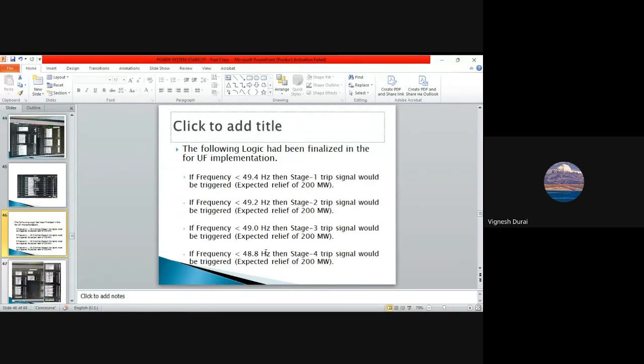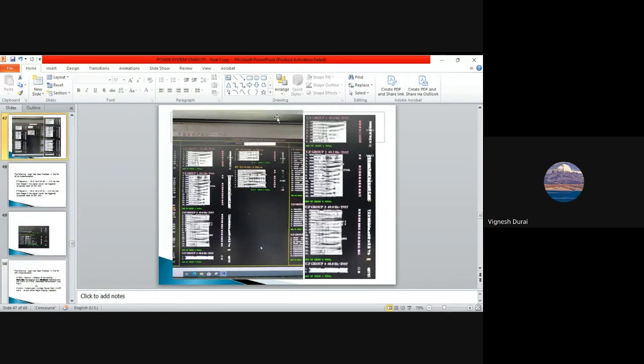This is how the under frequency relay tripping groups look, where we have 4 groups. You can see this. In every group we have a set of feeders which we should trip, and every SLDC has its own group of feeders which have to be tripped for under frequency.